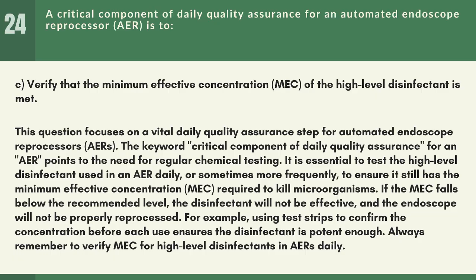If the MEC falls below the recommended level, the disinfectant will not be effective, and the endoscope will not be properly reprocessed. For example, using test strips to confirm the concentration before each use ensures the disinfectant is potent enough. Always remember to verify MEC for high-level disinfectants in AERs daily.